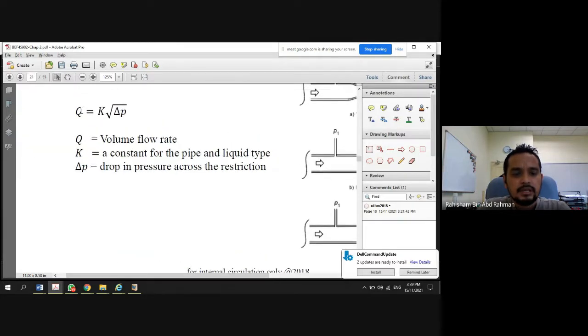Okay, the formula, as I explained, volume flow rate equals K, a constant, times the square root of the pressure difference, the drop in pressure across the restriction. K is a constant for the pipeline and the liquid type. So it means this constant is calculated based on the specification of the pipe as well as the liquid type, because there are various types of liquid, as we know.